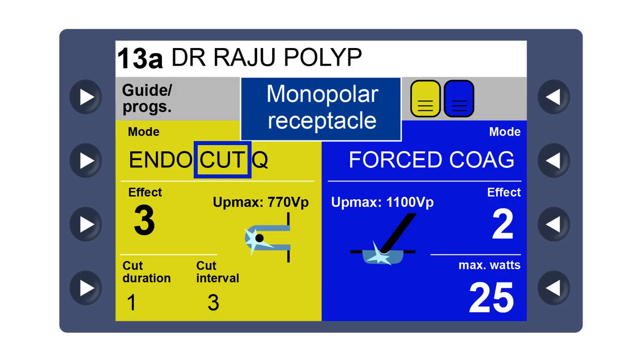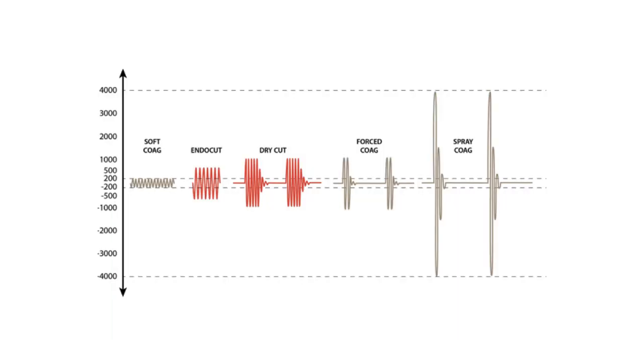Now, let us look at another important feature between the cut and the coagulation in terms of their voltage. So here, soft coagulation is a continuous cycle of less than 200 volts.